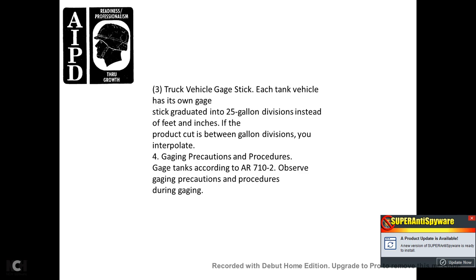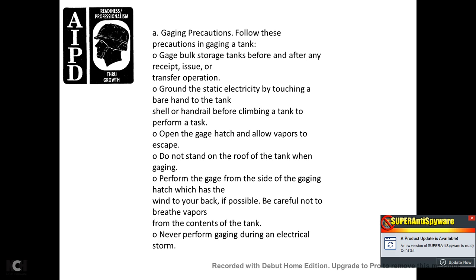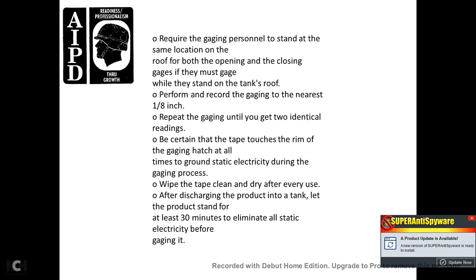16 & 17. Gauging precautions. Procedures for gauging tanks are in accordance with AR 710-2. Observe the following precautions: gauge bulk storage tanks before and after any receipt, issue, or transfer operations. Ground static electricity by touching a bare hand to the tank shell and handrail before climbing the tank. Open the gauge hatch and allow vapors to escape; do not stand on the roof of the tank when gauging. Perform the gauge from the side of the gauge hatch with the wind to your back if possible. Be careful not to breathe vapors from the contents. Never perform gauging during an electrical storm. Require gauge personnel to stand at the same location on the roof for both opening and closing gauges. Record gauging to the nearest one-eighth of an inch and repeat until you get two identical readings.